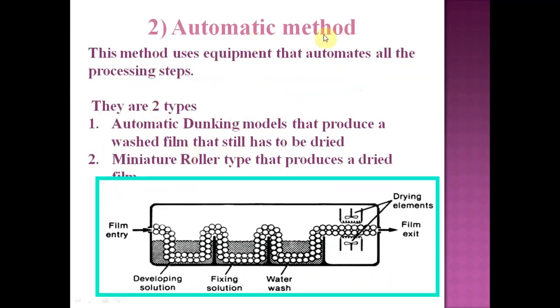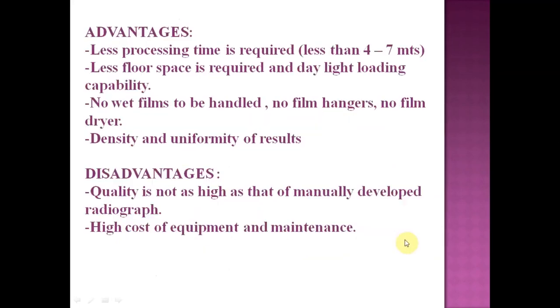The automatic method uses equipment that automates all the processing steps. There are two types: automatic dunking models, which produce a washed film that still has to be dried, and miniature roller-type processors that produce a dry film. The film goes through developing, fixing, washing, and drying automatically. Advantages: less processing time (four to seven minutes), less floor space, no wet films, no hangers, no dryers, and uniform density. Disadvantage: quality is not as high as manually developed ones, and the cost of equipment and maintenance is high.